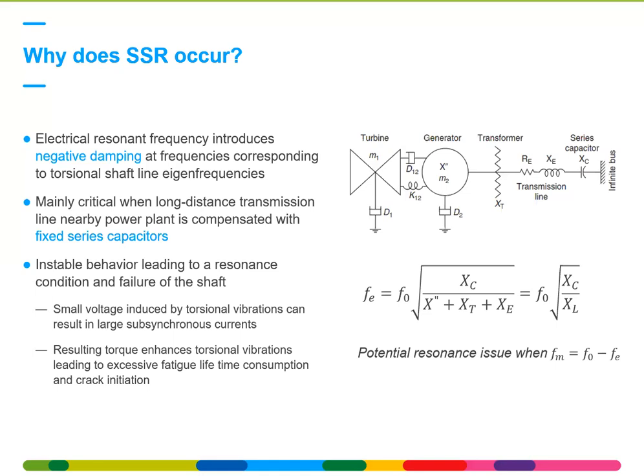So any disturbance will excite the natural frequency of the grid, and you will have subsynchronous currents on the grid. They will reach the generator due to the electromagnetic gap and the electromagnetic torque. They will excite the turbine. And if there is a match between the electrical grid frequency and the mechanical shaft line frequency and torsional vibrations, you could have an unstable regime. So this is one important example which has already caused a lot of damage on shaft lines.